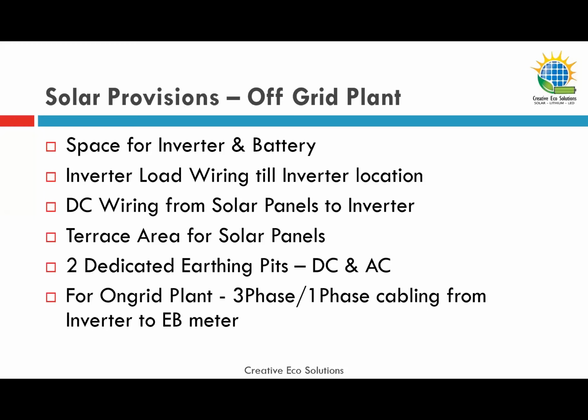Next is the DC wiring from the solar panels to the inverter. From your terrace, where the panels are installed, to the inverter location under the staircase or in the headroom, you have to plan a conduit. If the building is under construction, during the flooring or roofing stage, you can leave empty 1-inch pipes from the panel location to the inverter room, so that in future you can pull wires through them neatly. For existing buildings, we have to chase the pipes through the walls.